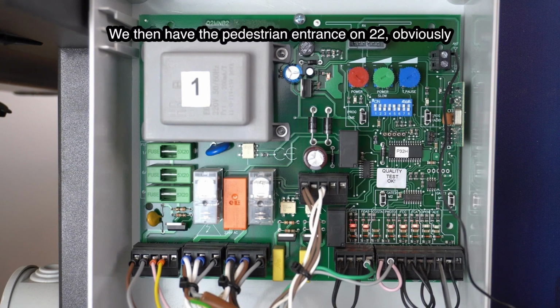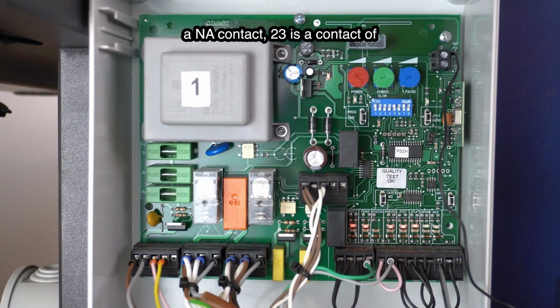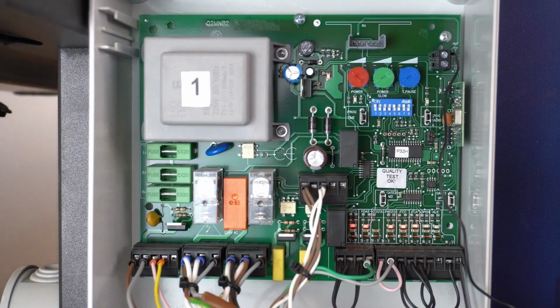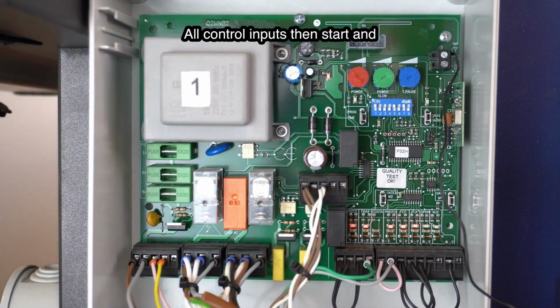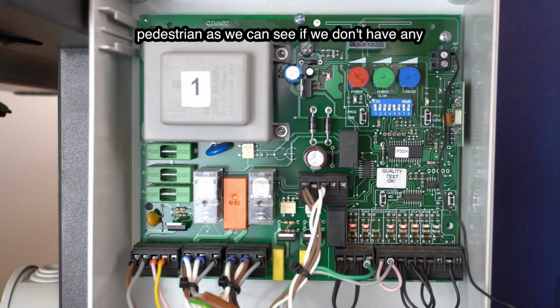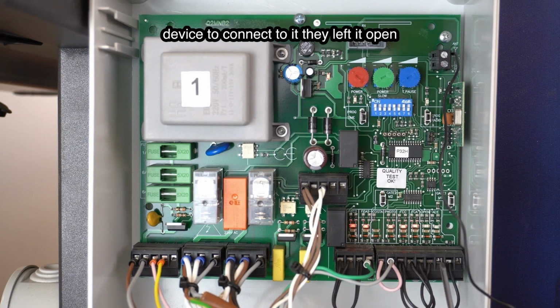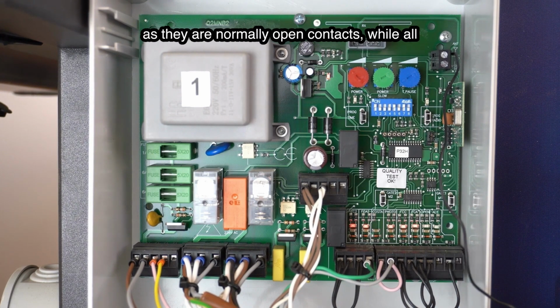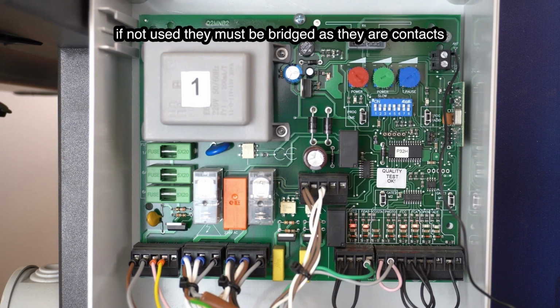Then we have the pedestrian entrance on 22, NO contact 23, and 24 is the common contact. The start input and all command inputs, start and pedestrian, as we can clearly see, if we don't have any device, are left open, since they are normally open contacts, while all the safety devices and limit switches, and unused contacts, must be bridged.